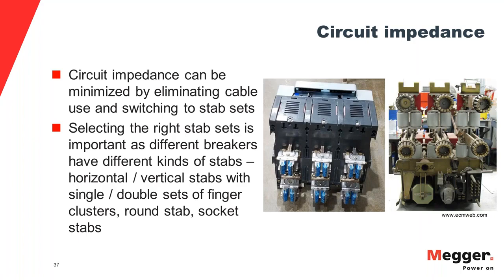One good way of eliminating or minimizing circuit impedance is by eliminating cable use altogether and going for stab sets. The challenge here is having the right stab sets on your test sets that are compatible with the stabs of the breakers, because breakers come in various shapes and sizes. They have all sorts of stab sets.